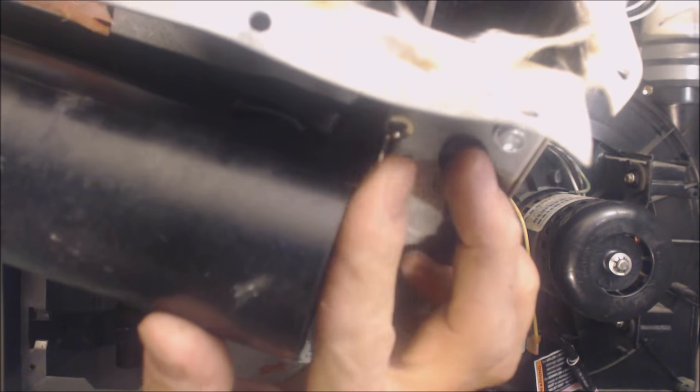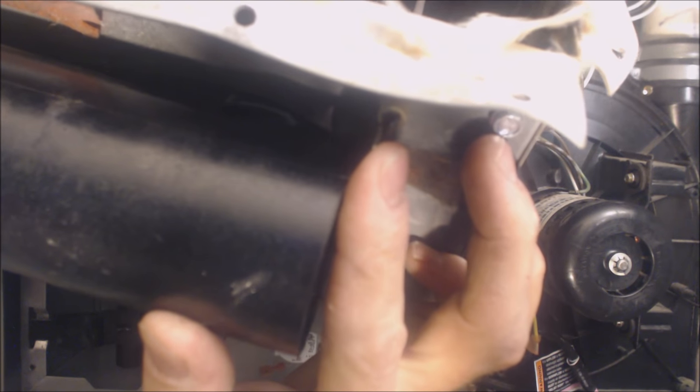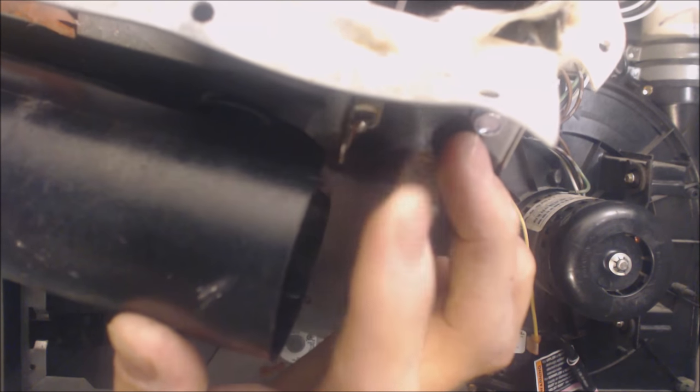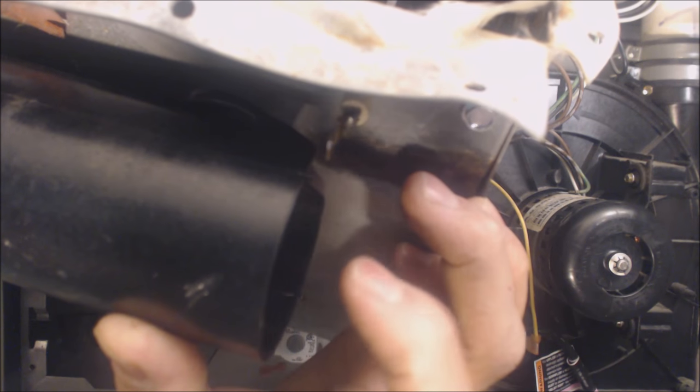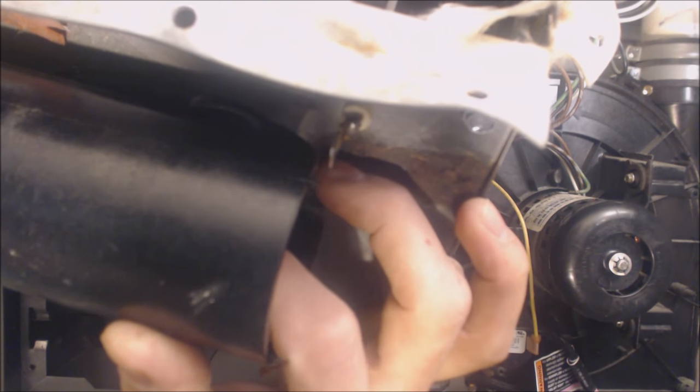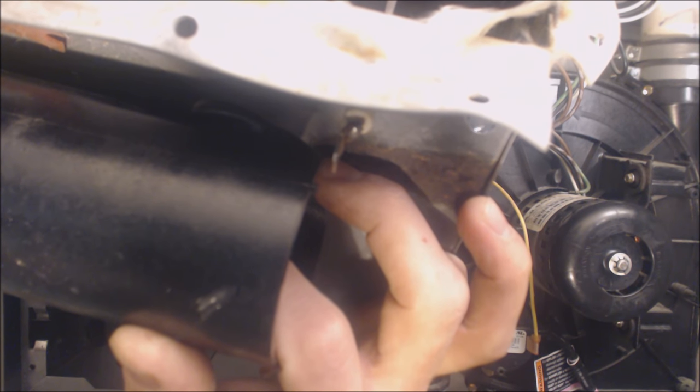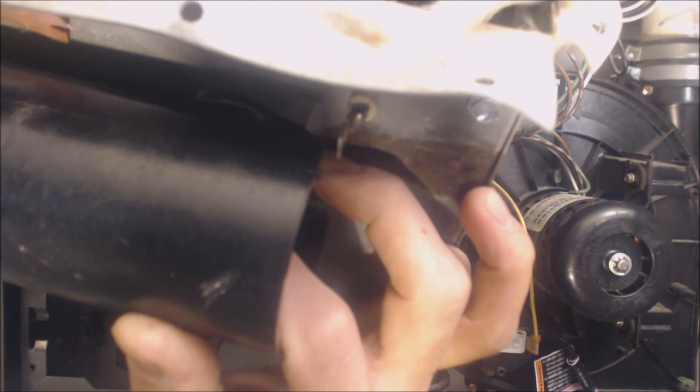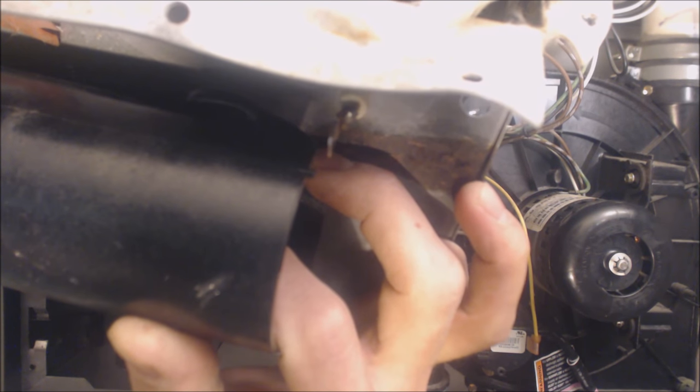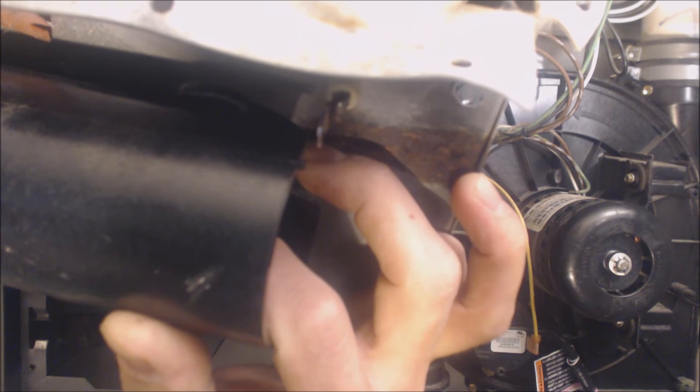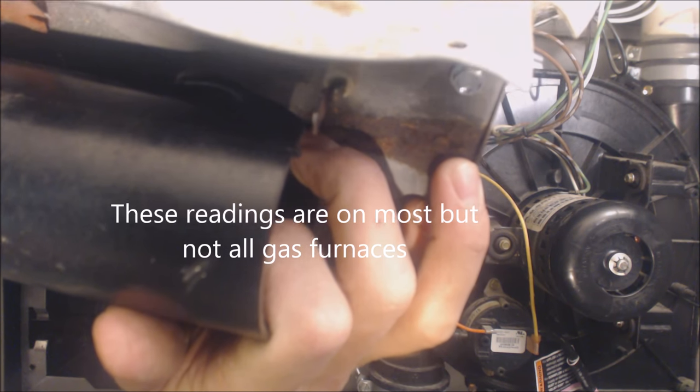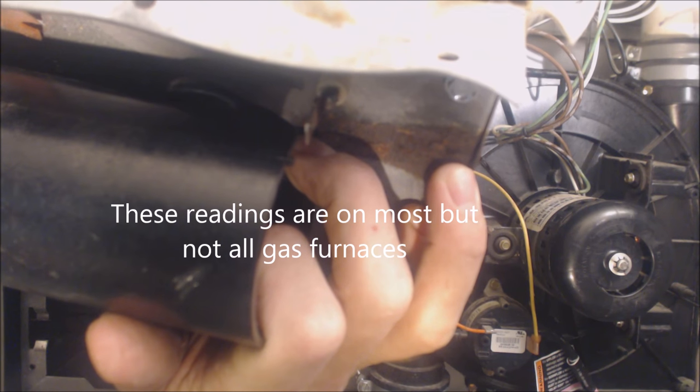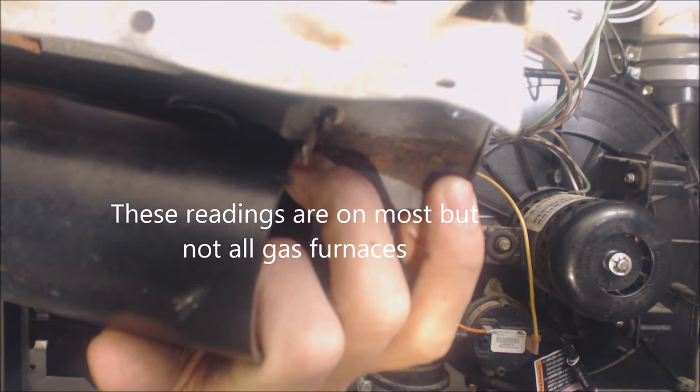By attaching one of the probes here and one of the probes to the wire that feeds this. And your multimeter is in between those in series. And you put it on micro amps DC, and then you can read while the flame is running your DC micro amps. And that reading is typically somewhere in the neighborhood of 3, 3.2 to 10 micro amps.